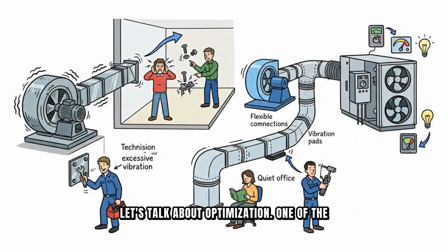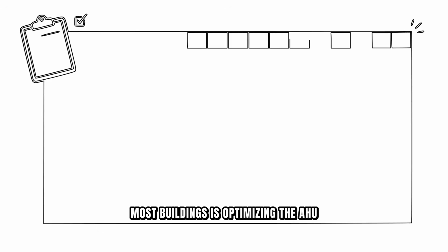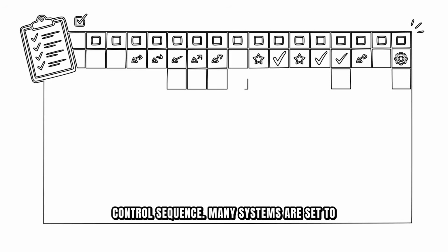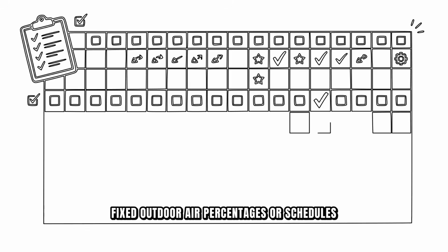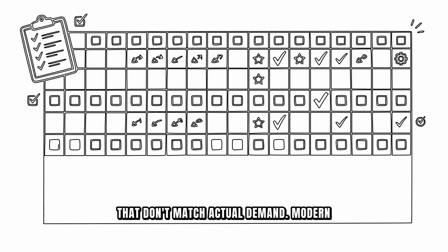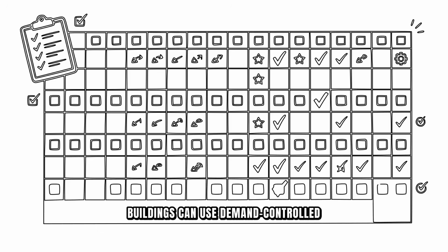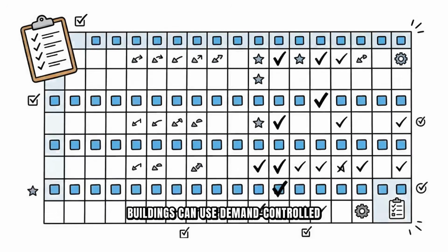Now, let's talk about optimization. One of the biggest energy-saving opportunities in most buildings is optimizing the AHU control sequence. Many systems are set to fixed outdoor air percentages or schedules that don't match actual demand. Modern buildings can use demand-controlled ventilation, where outside air increases only when carbon dioxide levels rise, indicating more occupants need fresh air.